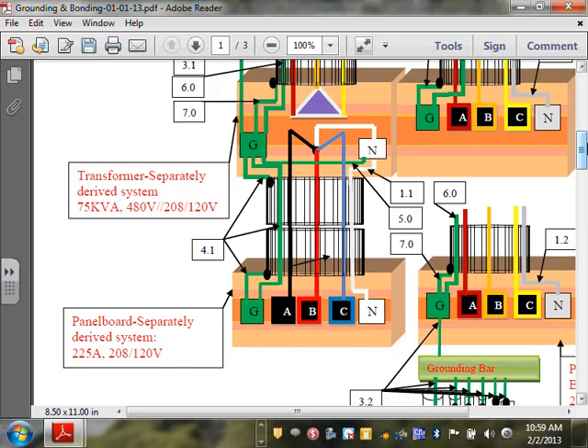Any comment, guys, about the equipment bonding jumper on the load side for this sub panel? Now, if you're coming with PVC, you don't have to worry about anything, right? All you have to do is mechanically attach the PVC to this box. If you're coming from underground, mechanically means it will be in a concrete slab, so it's really mechanically sound. It's not shaking. If this is coming to a panel, you have to have the fittings to attach it mechanically to the panel. Any comments? Any questions, guys? Anybody disagree? This is my understanding, especially the equipment bonding jumper, guys. Anybody has a different way, a different interpretation?